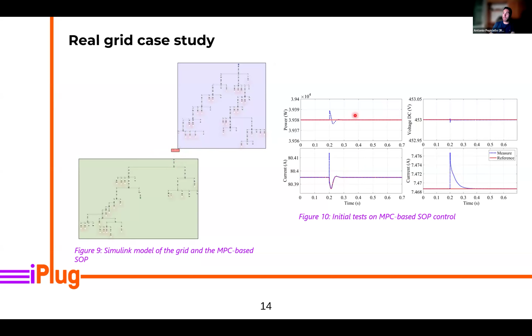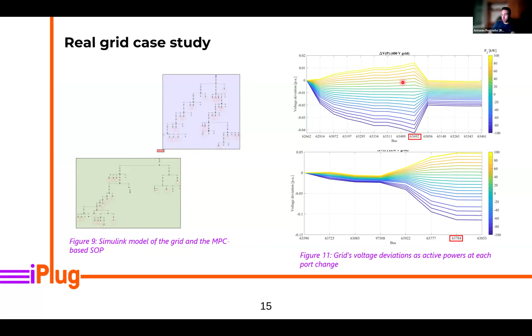In this slide, figure 11, you can see how by controlling the power flows in the different ports of the soft open point, we can have a large effect on the voltage deviations in both grids. Of course, if we consider that this is the position of the soft open point in the two grids, you can see how the effect is greater closer to the soft open point and it goes decreasing. But in any case, it's significant.